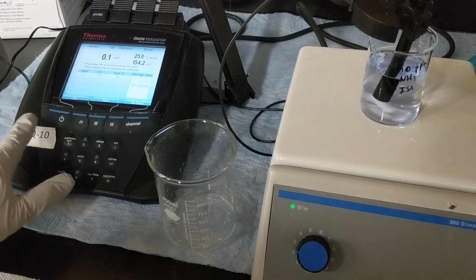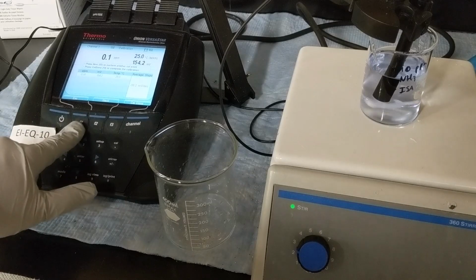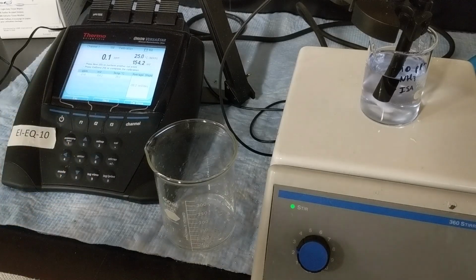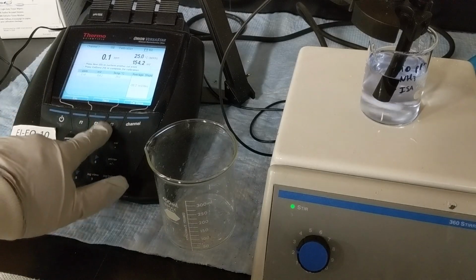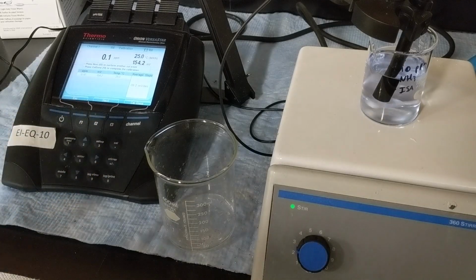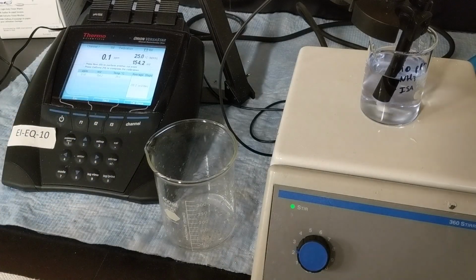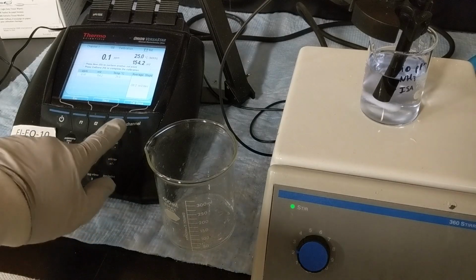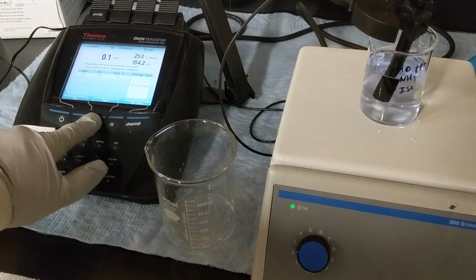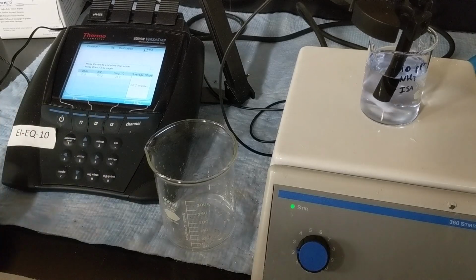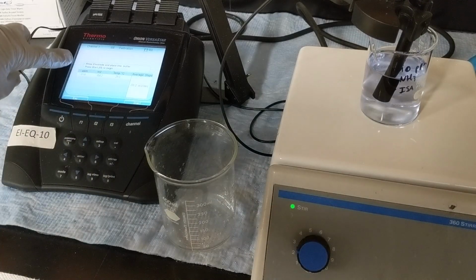And then once again, so now F1 is escape, which is basically get out of this calibration. F3 is cal done, which is to say I've calibrated all of my points and I want to use this as my calibration. I've only done one, so that's not what I want to do. F2 is next, so I want to hit F2, and then it gives me instructions again. Rinse the electrode, place it in the buffer, press start, F3 to begin.